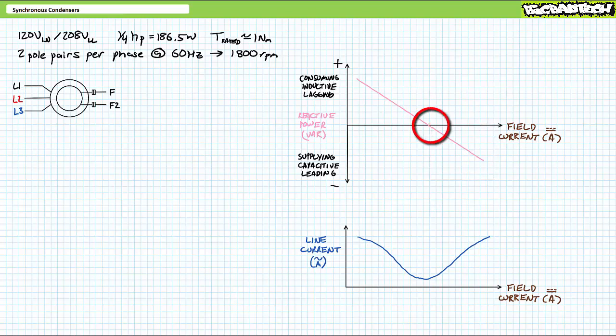We also learned that for an electrically excited synchronous motor in a given load condition, field current can be so managed such that the synchronous motor neither draws nor supplies reactive power and voltage and current are perfectly in phase — an occasion of unity power factor. A synchronous condenser is really an extension of these same scenarios, the one difference being the motor is mechanically uncoupled and free spinning. Since the motor is not doing any mechanical work, any excess reactive power it draws or supplies in this floating state can be put to work power factor correcting a larger three-phase AC system.